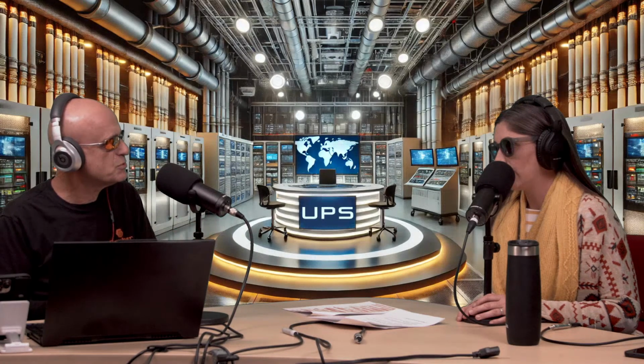You may want a generator, a genset. That's important because when your utility power drops and your static UPS is doing the work of continuing to supply power, it has a finite resource with your batteries. After 7 to 15 minutes or so, you're out of juice again.